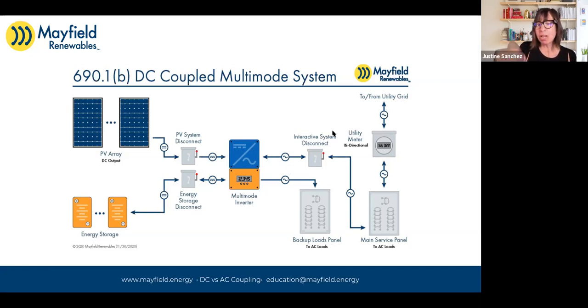Be limited by our interconnection. Let's say our interconnection is limited at a megawatt. Okay, so we're time shifting when we can utilize that PV array. But it's a way to build in a bigger PV array, which you couldn't do with an AC coupled system.